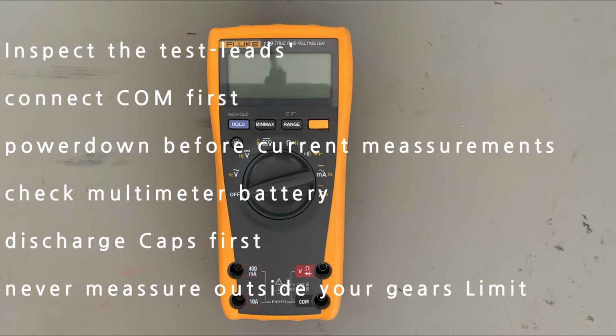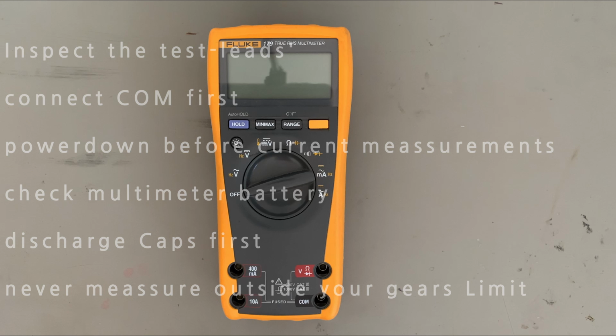Before every single measurement, 6 things. Inspect the test leads for damage, especially where the cable meets the plug and the probe. That is where they fail. Connect COM first, then the measuring lead. For current measurements, power down the circuit first, then break it, then insert the meter in series. Watch the battery indicator. A weak battery gives you wrong readings, not no readings. Discharge capacitors before any resistance or capacitance measurement, and never measure outside the specified voltage, current or CAT limits of your equipment. That takes 10 seconds and it is the difference between a routine day and a very bad one.